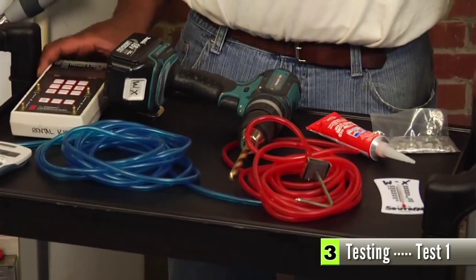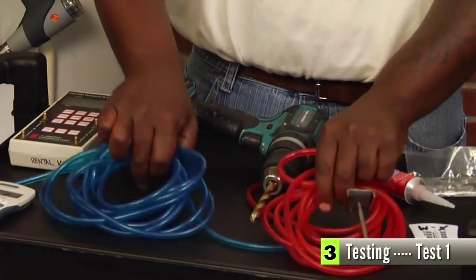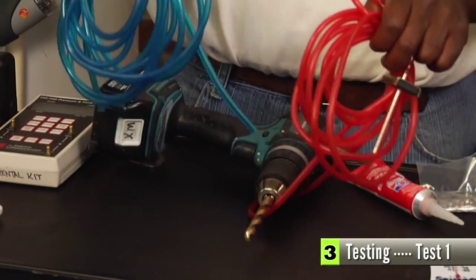The second pressure, gross worst case, is measured by finding the most negative pressure that can be created in the CAS when the exhaust fans and the furnace fan are turned on or off and the internal doors are open or closed. Again, the equipment needed for this test includes a DG700 pressure gauge, 2 gauge hoses, and the CAS depressurization limits chart. Before setting up the DG700 for testing, you'll need to determine if the CAS requires you to use 1 or both gauge hoses.